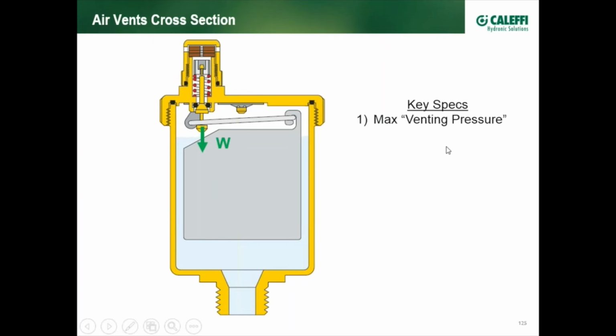Well, if it's exceeded, it can prevent the air vent from working, in which case the force W created from the weight of the float is more than offset by the force P caused by the internal pressure of the system. So for instance, if you have a 10-story building and down in the lower level mechanical room, perhaps you might want to specify 50 PSI be placed at the boiler, and an air vent is located down there that's rated 40 PSI, regardless of how much air collects in the bottom of the air vent, it will not work. The float would hang up with its weight not able to offset the force caused from the internal pressure.